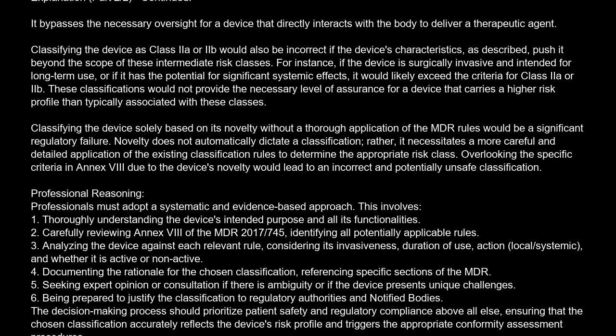Classifying the device as Class IIa or IIb would also be incorrect if the device's characteristics, as described, push it beyond the scope of these intermediate risk classes. For instance, if the device is surgically invasive and intended for long-term use, or if it has the potential for significant systemic effects, it would likely exceed the criteria for Class IIa or IIb. These classifications would not provide the necessary level of assurance for a device that carries a higher risk profile than typically associated with these classes. Classifying the device solely based on its novelty without a thorough application of the MDR rules would be a significant regulatory failure. Novelty does not automatically dictate a classification.